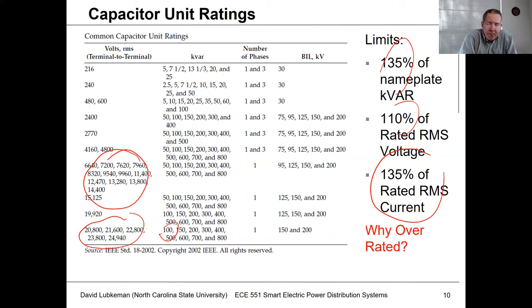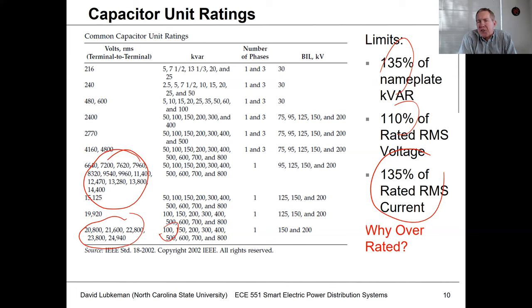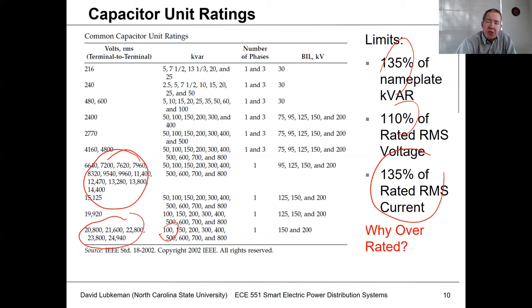Current in a utility distribution circuit doesn't just contain 60 Hz — loads generate harmonics at the third (180 Hz), fifth (300 Hz), seventh (420 Hz), and other orders. These harmonics add to the RMS current as well as RMS voltage. Capacitors are therefore overrated in current because if you have industrial loads generating harmonic currents, the capacitors need that additional headroom, otherwise they could be damaged by those harmonic currents.